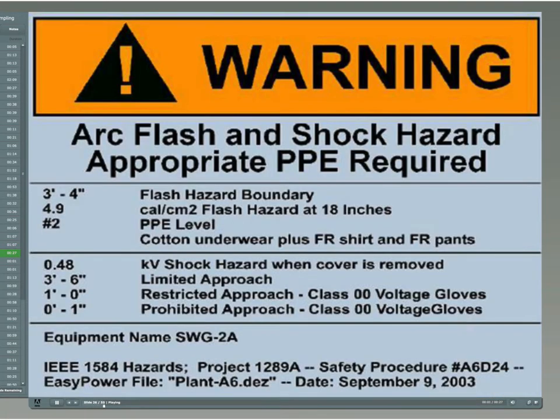This is an example of the labeling required by OSHA to instruct personnel in the exposure vicinity about the type of PPE to be wearing before exposure to this particular piece of equipment. Labeling is custom to each piece of equipment. Some pieces may require more protection than others. Some equipment owners are contracting with arc flash consultants to comply with the requirements of NFPA 70E.